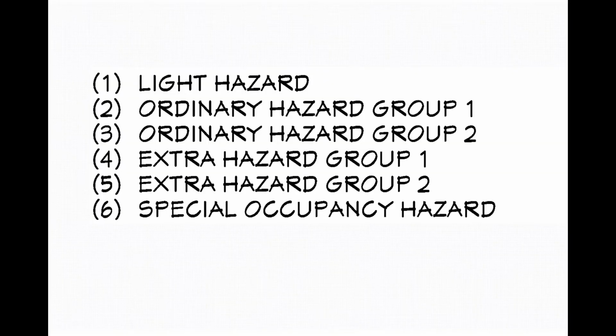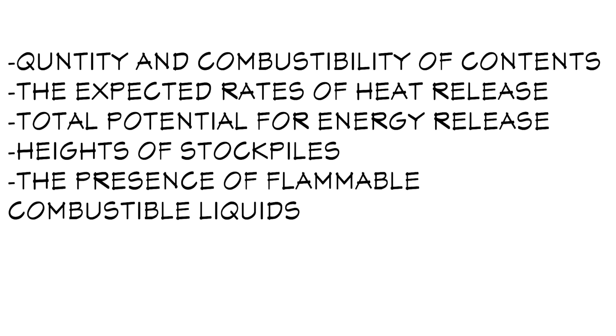NFPA 13 categorizes buildings or parts of buildings into these 6 occupancy hazard classifications. 1. Light hazard, 2. Ordinary hazard group 1, 3. Ordinary hazard group 2, 4. Extra hazard group 1, 5. Extra hazard group 2, 6. Special occupancy hazard. These 6 classifications are based on the quantity and combustibility of the contents, the expected rates of heat release, the total potential for energy release, the heights of stockpiles, and the presence of flammable and combustible liquids.